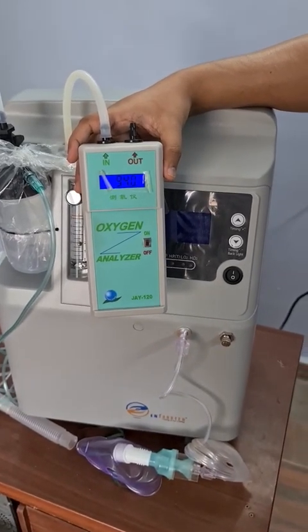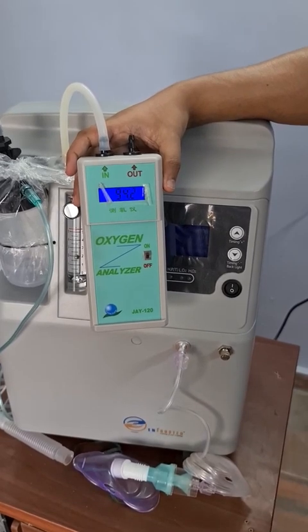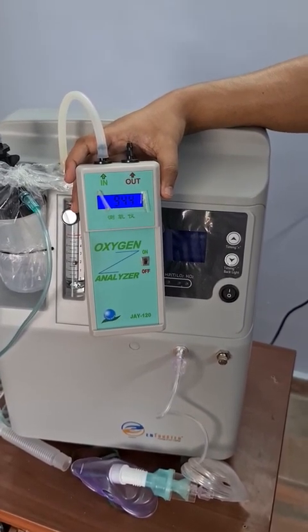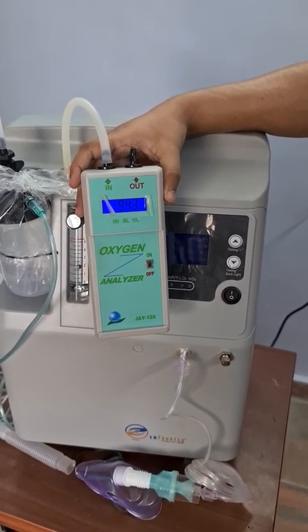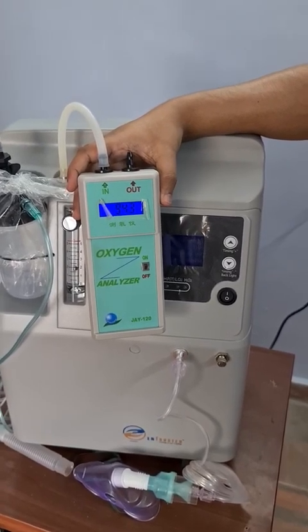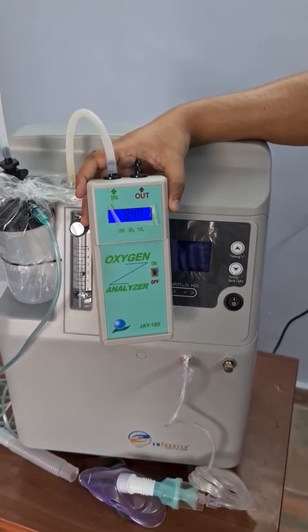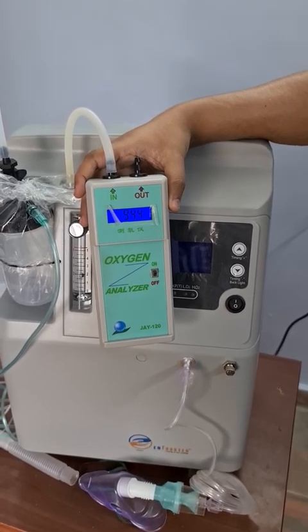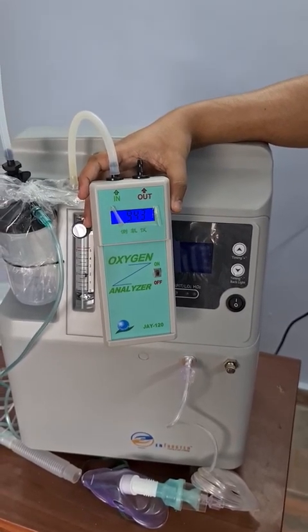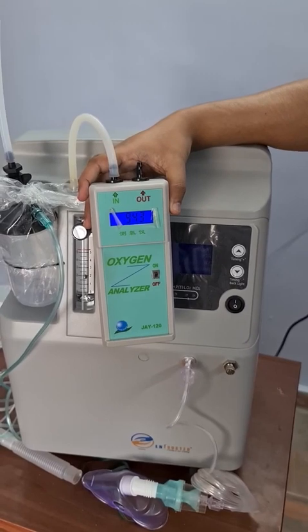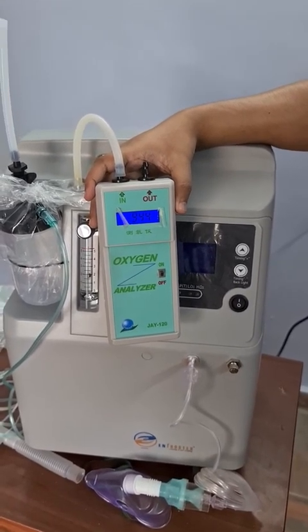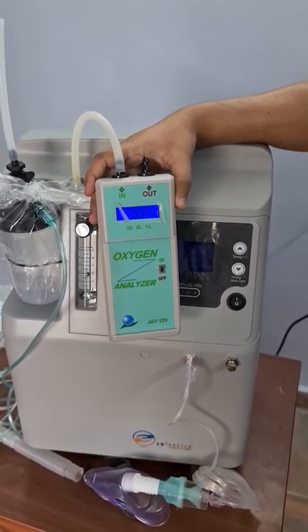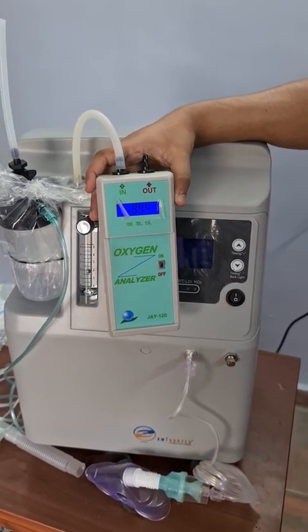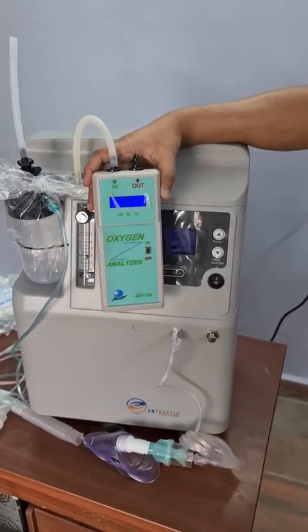Okay, now you can see the concentrator has almost reached 94.4% and it's keeping on increasing. So it's more than the guaranteed level which we are quoting to the customer. So now that we have checked the oxygen purity using the analyzer, the next few things I am going to tell you is how to connect the cannula to the in-patient, the proper way of connecting the cannula, and also what to do and what not to do.